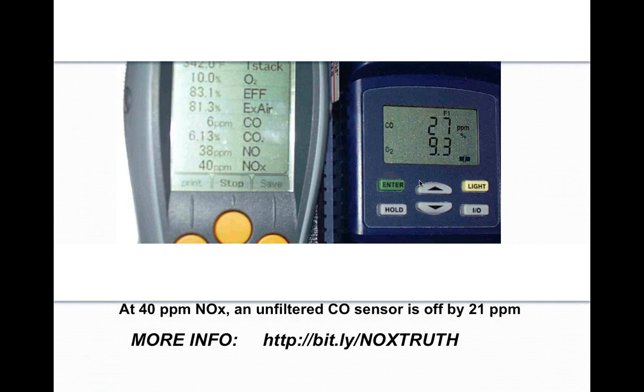So here are a couple products side by side. We're not doing any brand bashing here, but just to illustrate what you can see if you're running a combustion test with and without a NOx filter. So we have 27 parts per million being displayed on the instrument at the right, and only 6 parts per million CO on the left. Most people would think, because it has a lower number, something's wrong with the instrument on the left. In fact, there's something right with the instrument on the left.